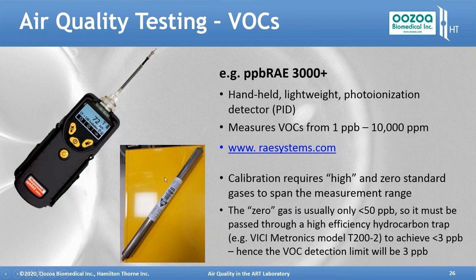This gas purification system, the hydrocarbon trap, is designed for purifying the carrier gas for gas chromatographs. And obviously you want to get all the stuff out of it before you start trying to measure what you've added in from your sample. And this device will achieve less than 3 parts per billion, which means that when we say our zero calibration is zero, it's actually less than 3 parts per billion. So our VOC detection limit will be 3 parts per billion. So we say, okay, it's undetectable. You wouldn't usually say zero, you'd say undetectable. And undetectable means it's less than 3 parts per billion.